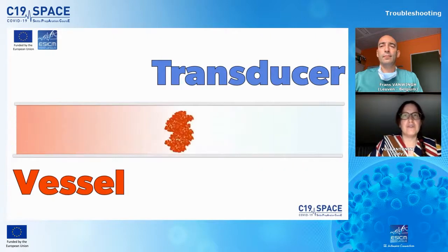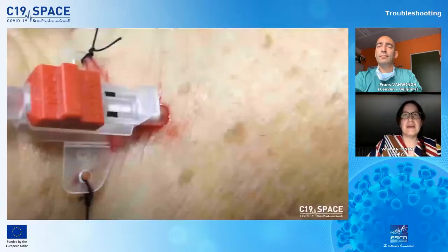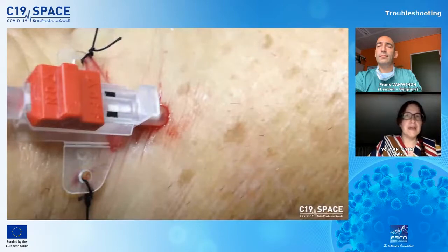Moreover, try not to modify the system, as the system is not compliant, meaning that the walls of the lines do not absorb the pressure, and it is calibrated to be at a fixed length. Removing, adding or replacing any component impairs its integrity and its reliability. So please avoid any manipulation of the system. Be aware you could have kinking also at the catheter level, particularly if the patient is awake and with radial arteries.